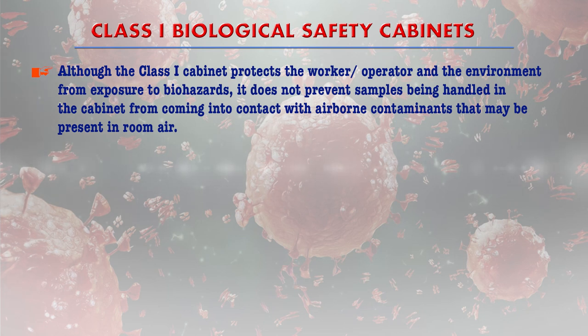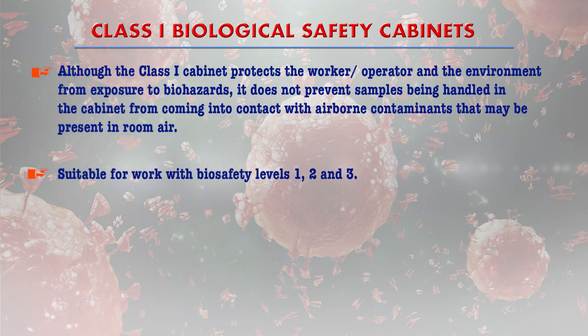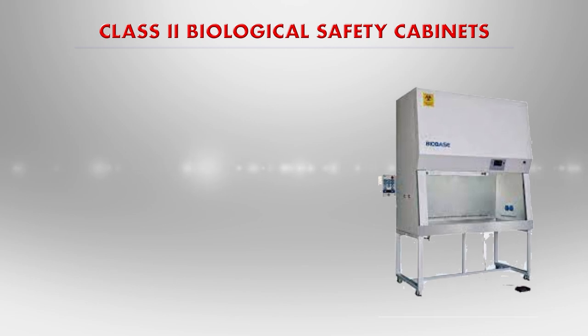Although class 1 cabinets protect the worker, operator, and environment from exposure to biohazards, they do not prevent samples being handled in the cabinet from coming into contact with airborne contaminants present in the room air. Class 1 cabinets are more suitable for work with biosafety levels 1, 2, and 3.